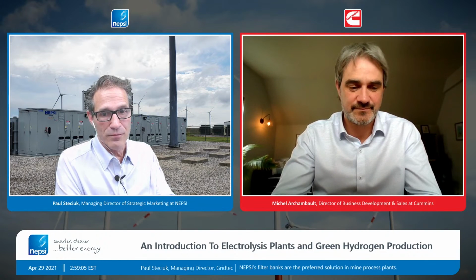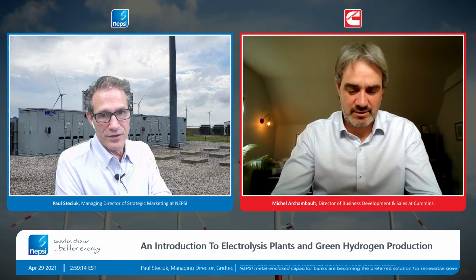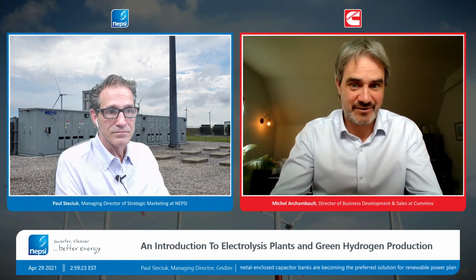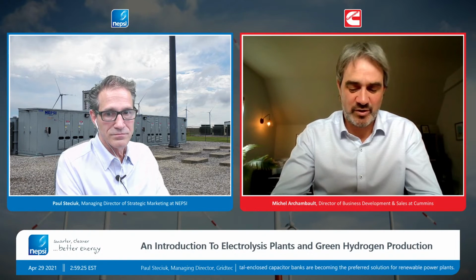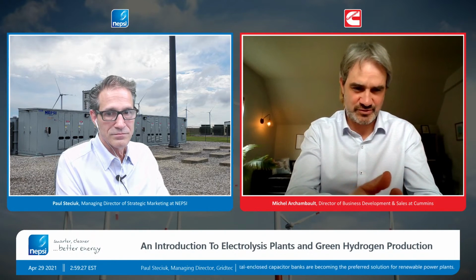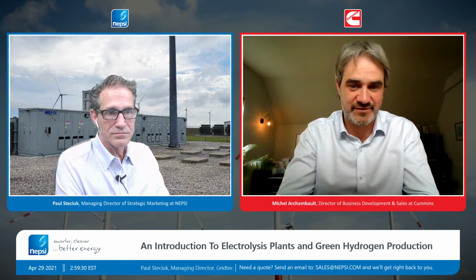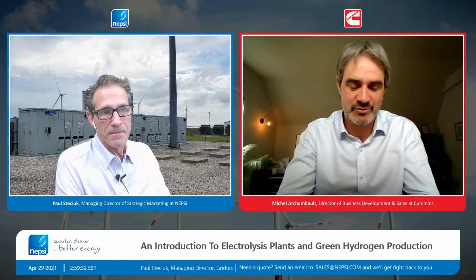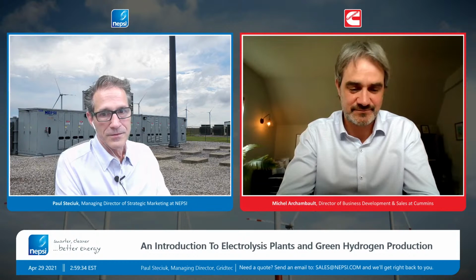Is it possible to use the small size of the system for backup of electrical substations, for protection relays and electronic measurement power supplies, instead of battery chargers or UPS? So small size systems for backup power - it's again possible, you can put a backup generator, a fuel cell generator. In the earlier slide, I showed the solid oxide fuel cell that can be a perfect fit as well for that application. But you can also put PEM fuel cells.